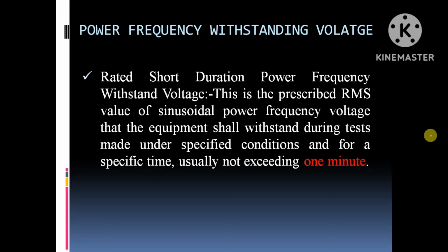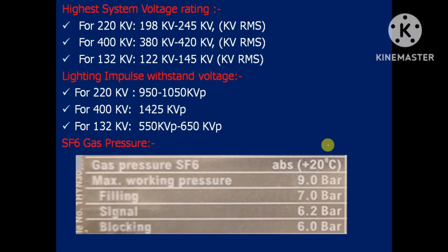So one more is the power frequency withstand voltage. This is the RMS value of the sinusoidal power frequency voltage that the equipment shall withstand during the time of test under specified conditions for a specific time, usually not exceeding 1 minute. This is the highest system voltage rating; as I told you, this is 220 kV. The highest system voltage can go up to 245 kV, whereas the lowest voltage can go down to 198 kV. These are the range of voltages for a 220 kV substation. For 400 it will be 420 and 380 kV. The lightning impulse withstand voltage for a 220 kV substation is 950 to 1050 kVp, kilovolt peak, and for 400 kV it is 1425 kVp.